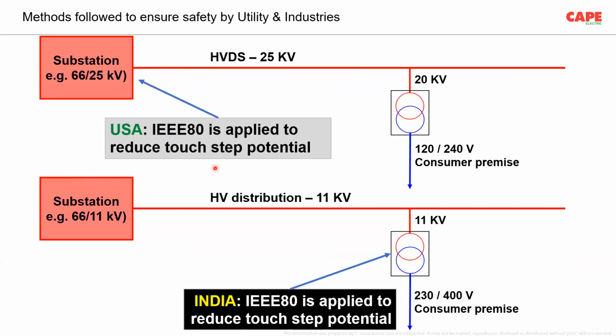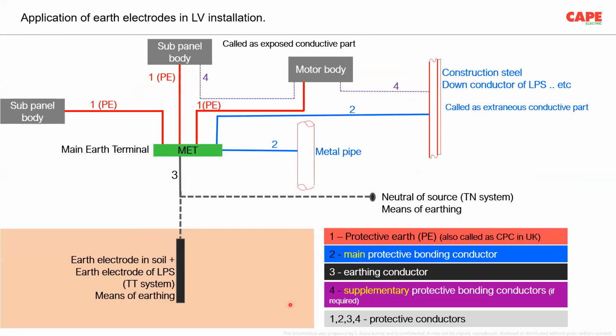So what I wanted to tell you is, even though the earth enhancing compounds are written in several standards, please understand that behind it is a reason, predominantly about the low voltage electrical installation in the sense of a consumer premise, probably with a transformer of 11 kV, 22 or 33 kV. Under that condition, the earthing principles explained in it are practically not applicable. This is what I confirm. Then what exactly should you do for a consumer premise? It is protective equipotential bonding. Protective equipotential bonding means you have to interconnect all the metal in your building in such a way that the touch and step voltages are lesser.